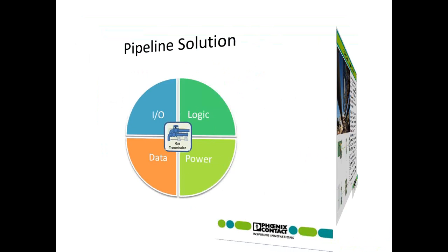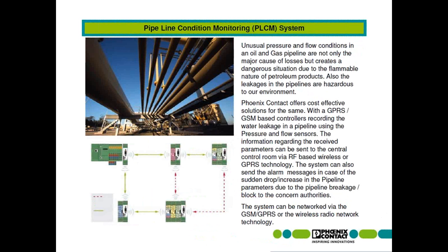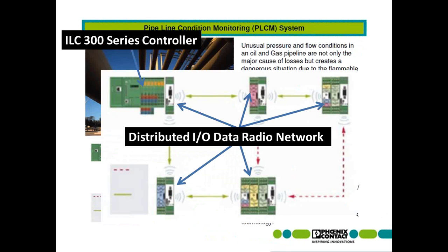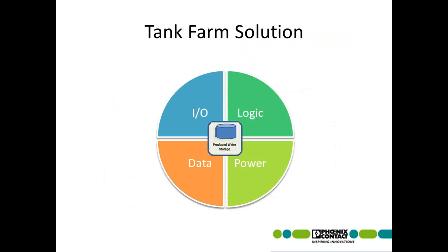Looking then to the pipeline solutions that we offer, again, we look at our data radios and ILC controllers. In this particular example, we would configure a SCADA layout using an ILC 300 series controller with the suitable I/O arrangements through our networked data radios. Allowing you to communicate over long distances, any number of configurations required for monitoring the safety of a pipeline, whether it be cathodic protection, leak detection, or general maintenance issues on the system.